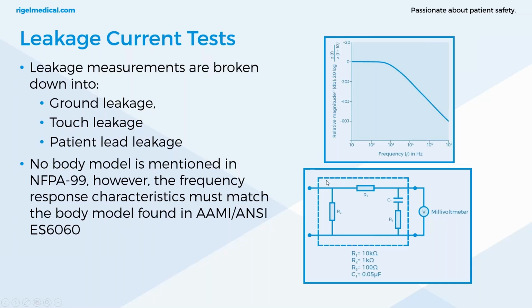Without putting myself out of a job, you could, of course, make this up in your own workshop with a voltmeter and some basic components, resistors, capacitors. You would also need to simulate the fault conditions such as open ground, which is found in NFPA 99. That's one of the reasons why workshops do use dedicated safety analyzers, and it just ensures that you're getting the right measurements.